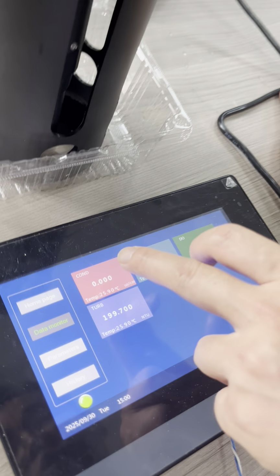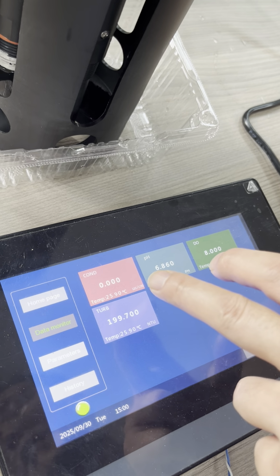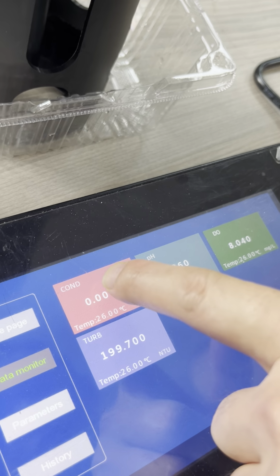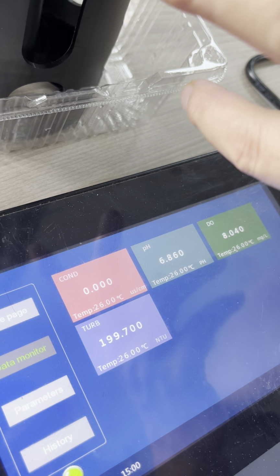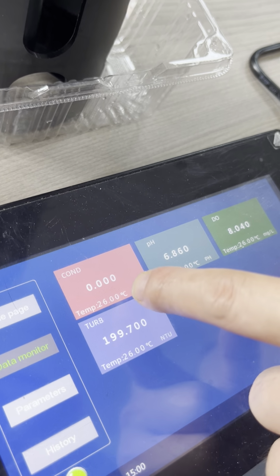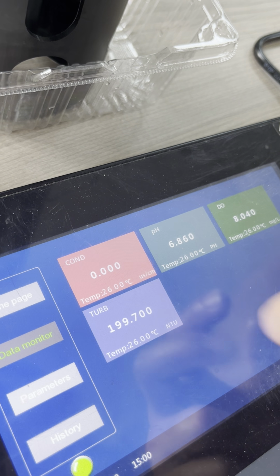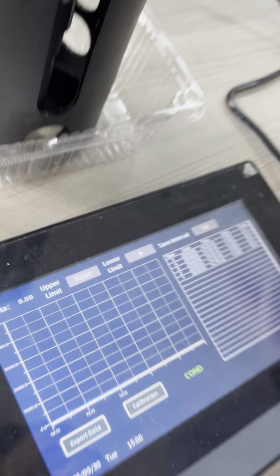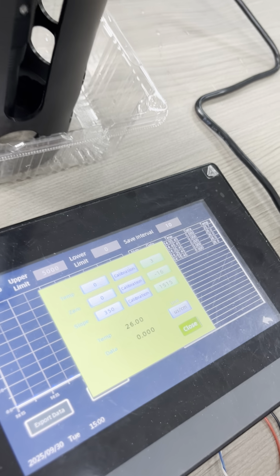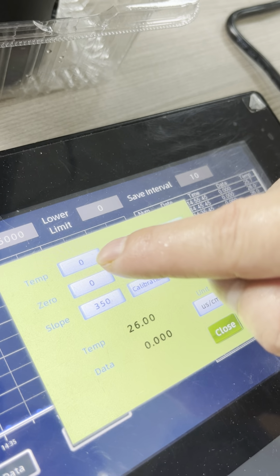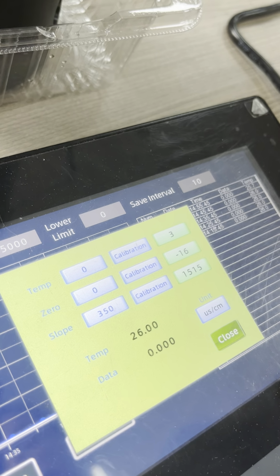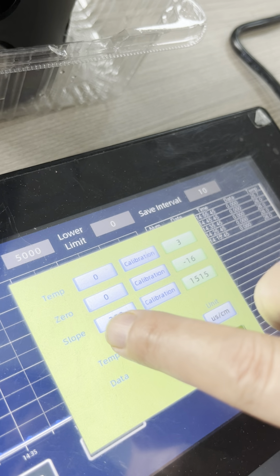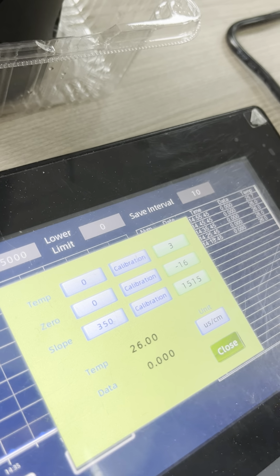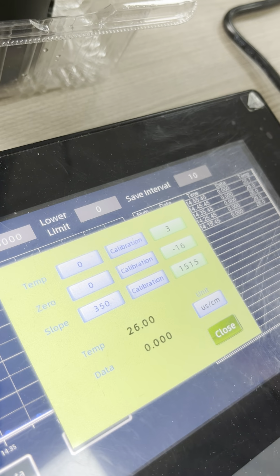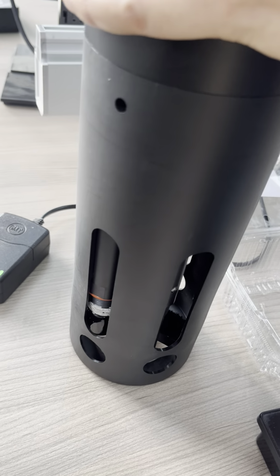At last, we will do the salinity calibration. Because I do not have a salinity sensor here, I just use the conductivity sensor as an example. You click here, click calibration. There's no need to do temperature calibration. We will do zero and slope calibration. For zero calibration of the salinity sensor, we put the sensor just outside.